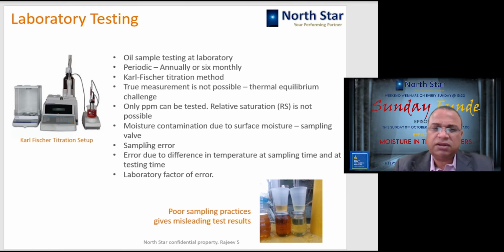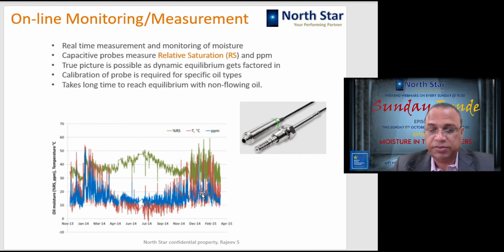There are sampling errors, wrong methods of sampling. If you see this photograph, this is how the oil sample is taken for testing. This looks like some candy bottle, and here is a classic mineral oil water bottle. If the sample is taken in such a way, you may get other parameters right. You may get, if you're lucky, DGA right. You may get BDV also right. But of course, moisture, which is a very sensitive parameter, will go inside this bottle and give you a wrong result. So because of all these reasons, laboratory testing has its own limitations.